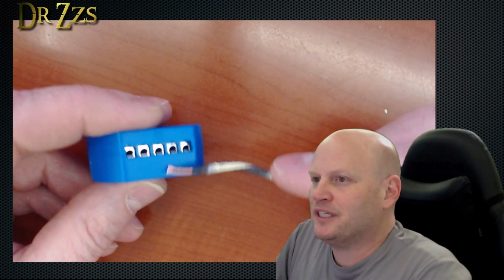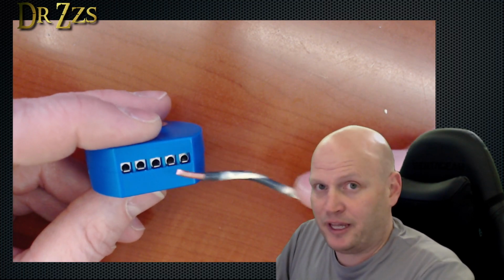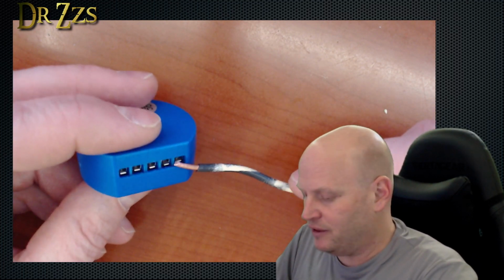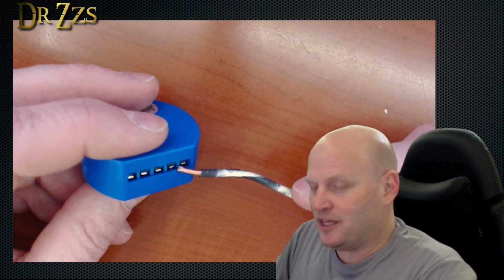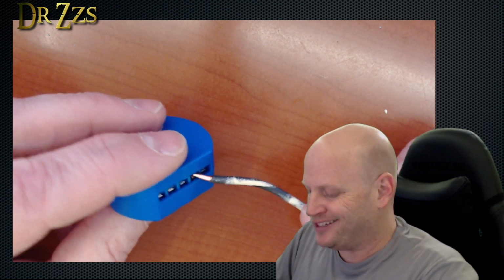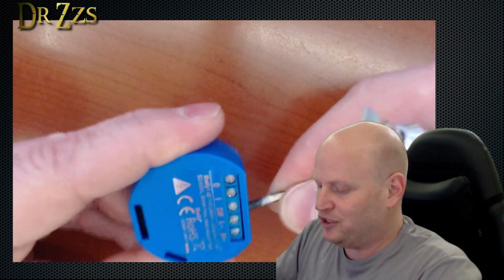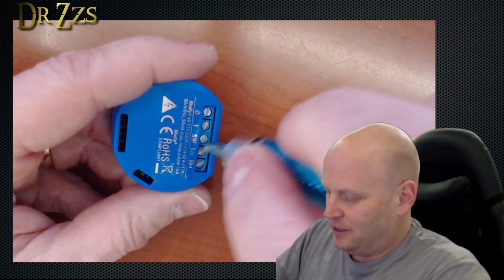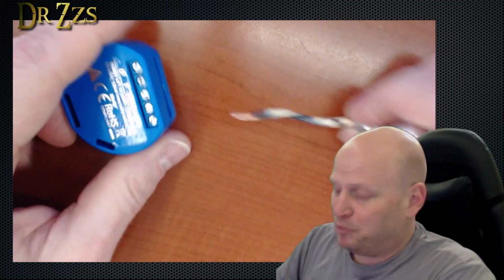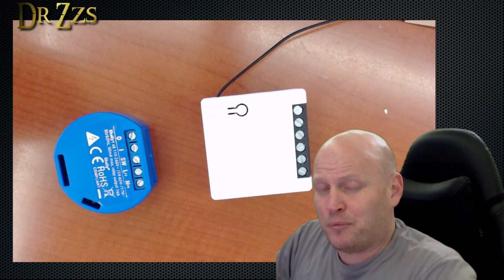Part of the problem, I think, with these connectors is when you fill them, like I'm filling them with this wire that barely fits in there, the mechanism that they use to hold the wire in place doesn't really get a chance to do its job correctly. Tighten it down. Still can pull it out. Still easier to pull out. So that was solid copper wire.